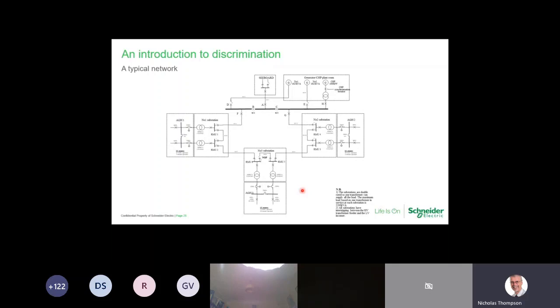So we've got number one substation, for example, with two ring main units, RMUs, on there, and then when we go onto the LV side, we've got the LV devices. We've got the primary LV protection, then we're going downstream onto the second LV device there as well. So what we would do in a very simple scenario on this one here, we would look at this area here. We don't need to worry about that bus section because there probably isn't any protection on there. So we're going to be looking at this area here for this particular example.